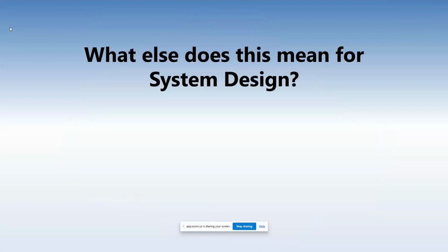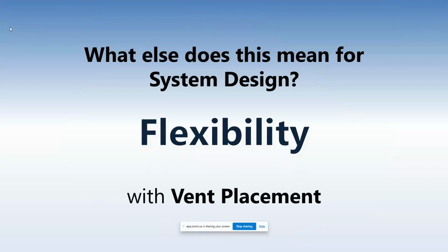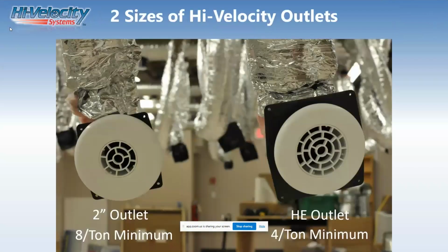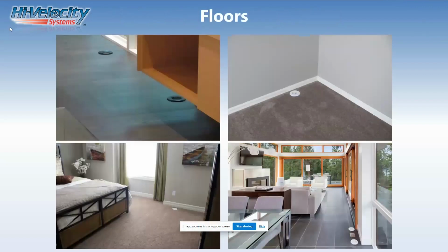So again, what does this mean for system design, flexibility, and vent placement? Well, we've got two sizes of outlets. We've got a 2-inch and an HE. Well, what's an HE? HE is 2 7/8. It's double the volume of a 2-inch outlet. Usually a 2-inch outlet will go in a bathroom. The HE goes into the bigger rooms.